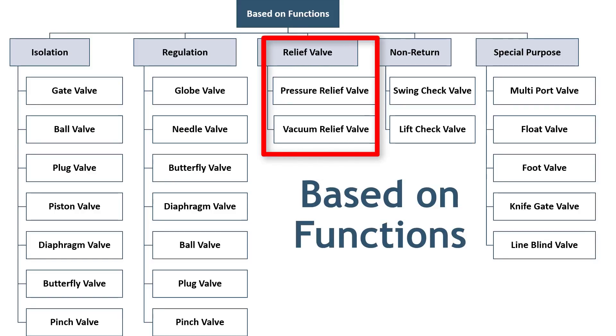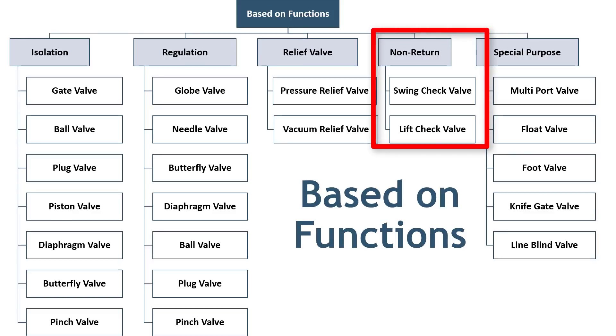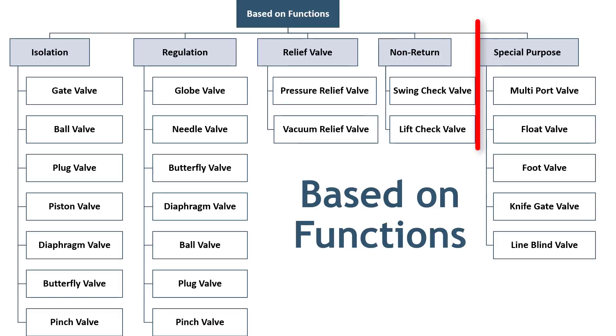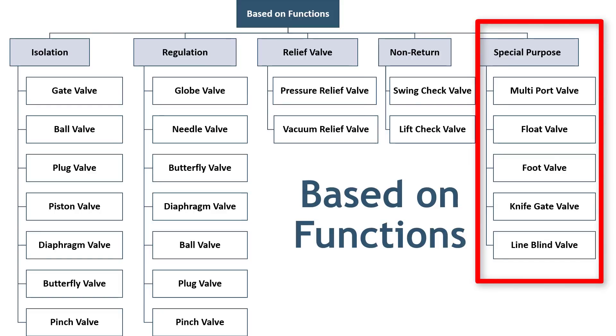Pressure and vacuum relief valves are used to prevent overpressure and vacuum in the system that can damage the piping and equipment. Non-return valves such as swing and lift check valves prevent backflow. Some valves are designed to serve a special purpose, such as multiport, knife, and line blind valves.